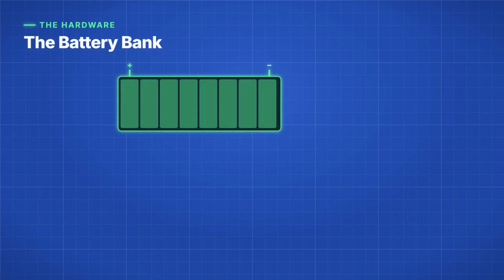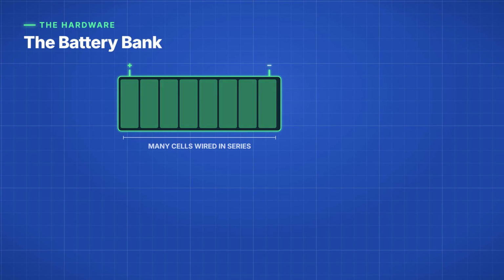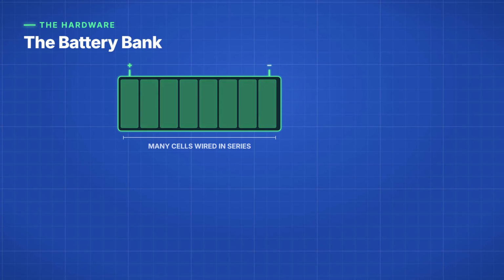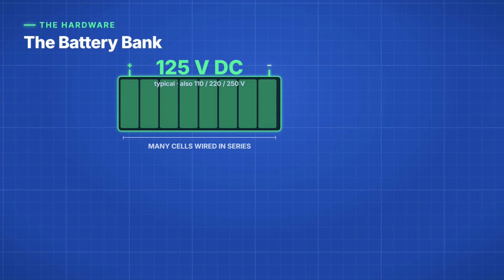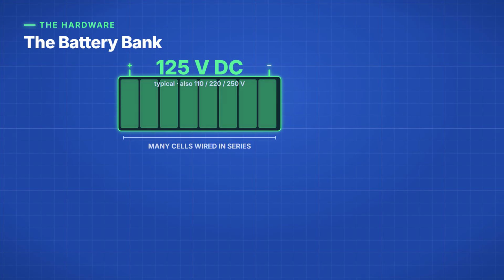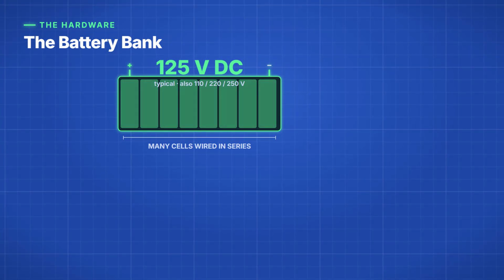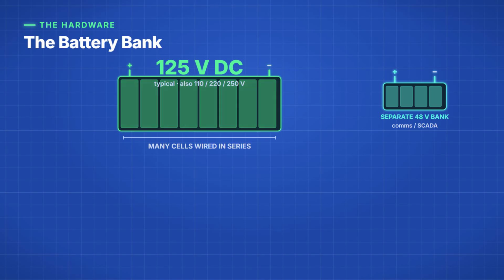Now let's look at the battery bank itself. It's built from many individual cells wired in series, so their voltages add up to the level the substation needs. Most banks sit at around 125 volts DC. You'll also find 110 volts, and on large transmission sites, 220 or 250. The communications equipment often runs from its own separate 48-volt bank.